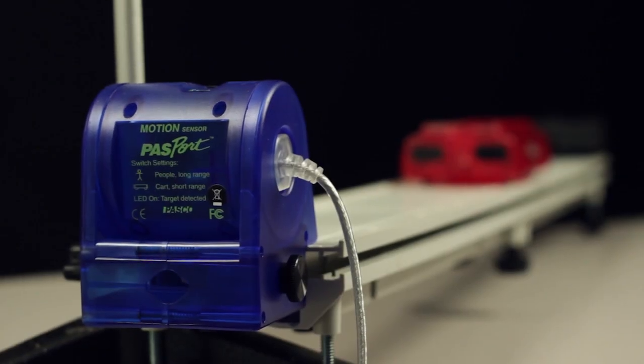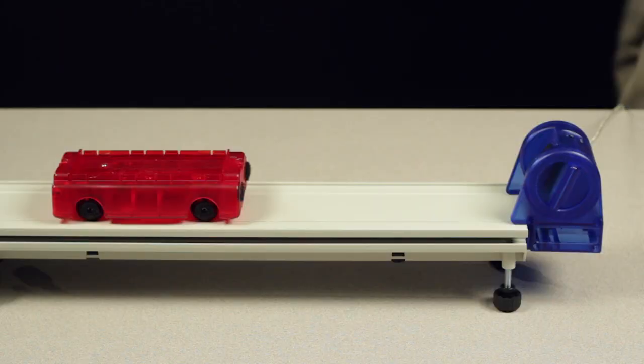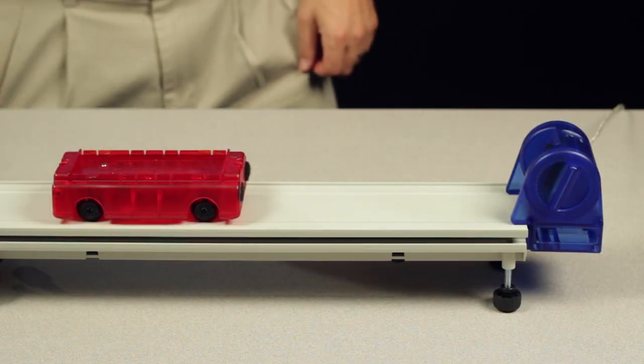Because the sensor uses ultrasound, it's sensitive to obstructions that may block or be near the target object when making measurements. Be sure to clear any of these obstructions from the one-dimensional path of the sensor when making measurements.